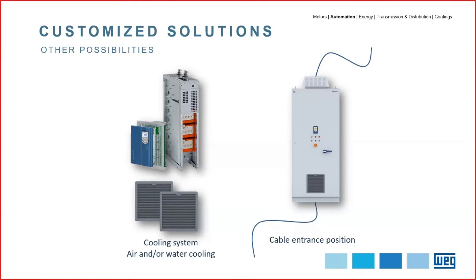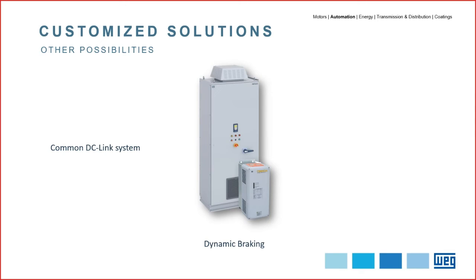Customized cable entrance position. So it's possible to follow the electrical room project, where sometimes it may require cable entry from the top, from the bottom, or from the side of the enclosures. We can customize the common DC link system, saving space due to the smaller quantity of panel components that will be necessary compared to running all individual drives, each inside its own enclosure. We can add a dynamic braking. This is mostly used in 6-pulse VSDs to dissipate the energy generated when the load must be quickly slowed or stopped.